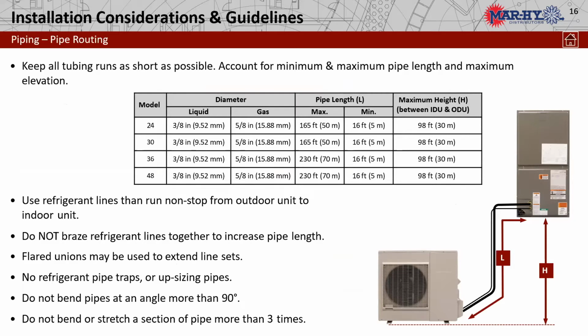Okay, line sets. Let's talk about line sets. So, the one thing nice about this, the 20 through 48, the 2 through 4 ton, they all use the same size line set. That'll be 3/8, 5/8. The 24 and 30, they are good up to 165 feet. We need a 16-foot minimum. Now, don't call me and ask me what happens if we go closer, because I know it can't be good. Remember, there's noise issues, there's oil return. I'm going to tell you what we see right here.